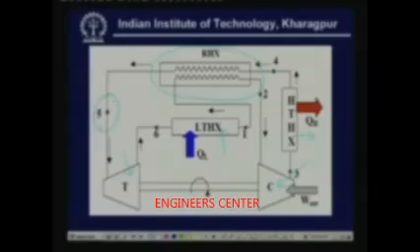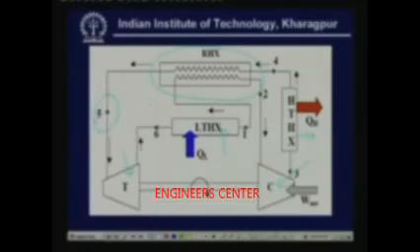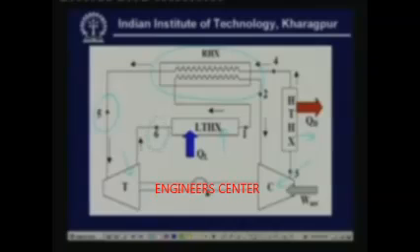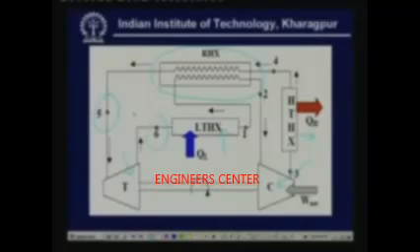In the regenerative heat exchanger, cold air coming from the low temperature heat exchanger extracts heat from the hot air that is going to the turbine. As a result, you are able to pre-cool the air going to the turbine, and the temperature at the inlet to the low temperature heat exchanger will be reduced. This is the purpose of using a regenerative heat exchanger.